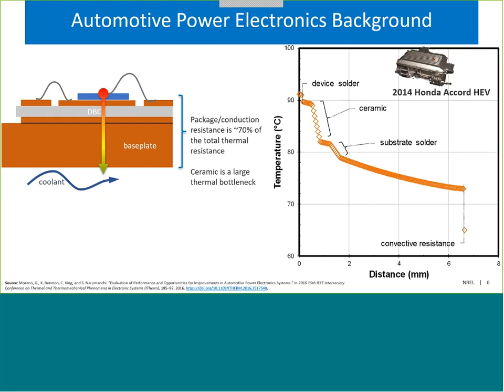From these modeling results, we estimate that the package, or the conduction resistance, is about 70% of the total thermal resistance. That's the resistance from the device all the way to the bottom of the base plate. The convective resistance, which is from the bottom of the base plate to the fluid, only accounts for about 30%. Within the package, the ceramic typically makes up the largest thermal resistance. One way of improving the thermal performance is by reducing that conduction resistance through elimination of some of these package layers. In today's presentation, I'll talk about a cooling strategy that we're looking at that allows for removing the ceramic layer by using a dielectric fluid to cool the module.